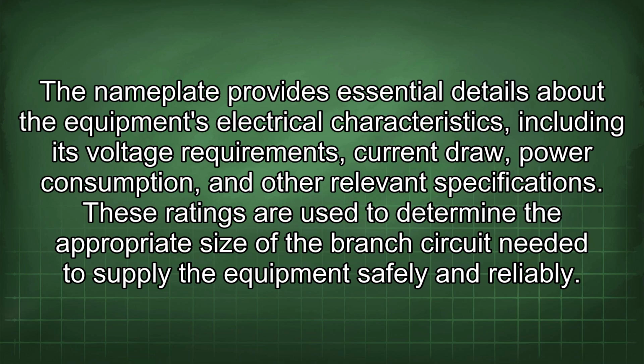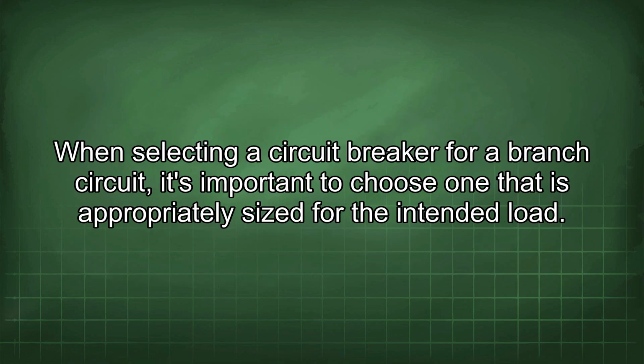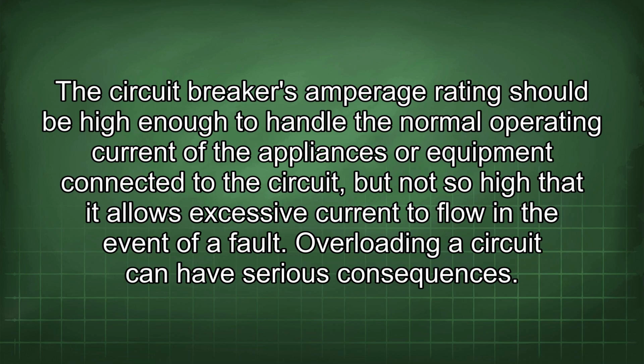When selecting a circuit breaker for a branch circuit, it's important to choose one that is appropriately sized for the intended load. The circuit breaker's amperage rating should be high enough to handle the normal operating current of the appliances or equipment connected to the circuit, but not so high that it allows excessive current to flow in the event of a fault. Overloading a circuit can have serious consequences.